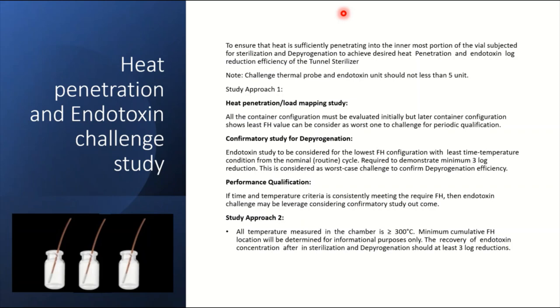For performance qualifications, if the time and temperature criteria is consistently meeting the required Fh, then endotoxin challenge may be leveraged, considering the confirmatory study approach. All temperature measurements in the chamber greater than 300 degrees and minimum accumulated Fh located to be determined for information purpose only. The recovery of endotoxin after depyrogenation tunnel should be at least three log reduction.